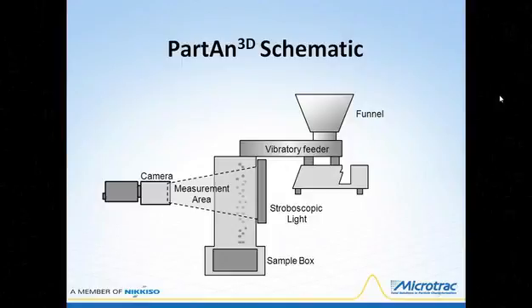Here's a schematic showing the simplicity of the Partan 3D's dynamic image analysis method. The dry sample placed in the funnel above moves on the vibratory feeder to the edge of the sensing zone, where it falls by gravity through the sensing zone and is collected in the sample box at the bottom. A light strobe on one side lights the particles as a digital camera on the other side photographs them as they tumble through. A video file is stored and distributions and summary data for 32 morphological parameters are calculated and reported, typically in one to two minutes.